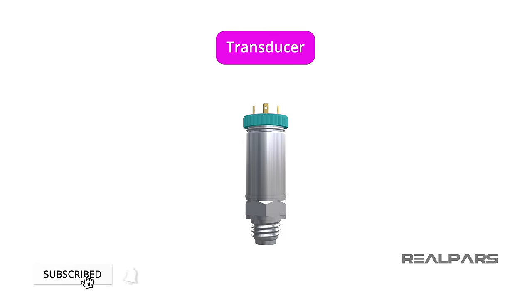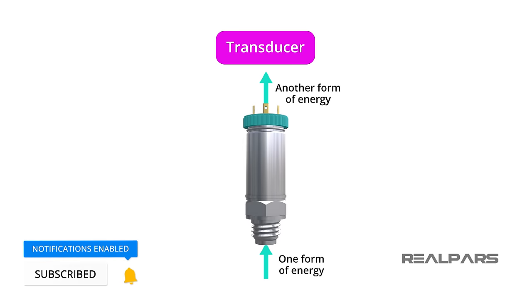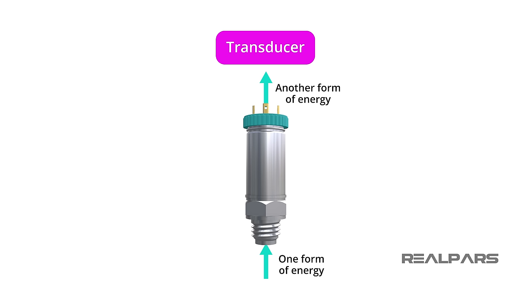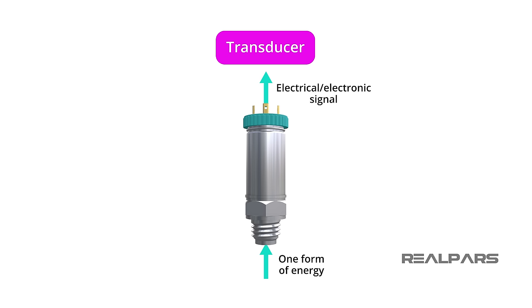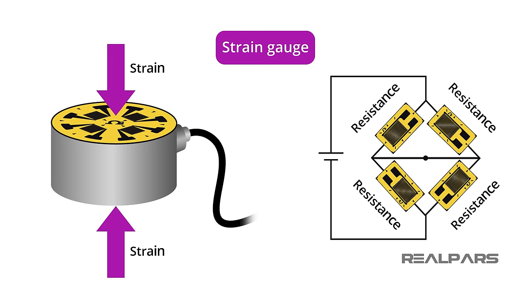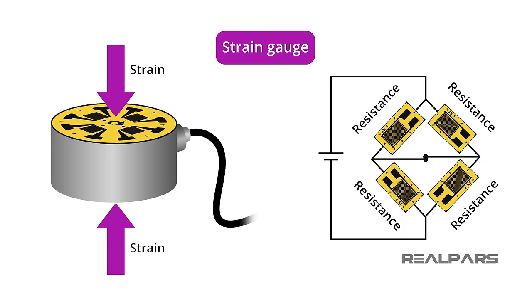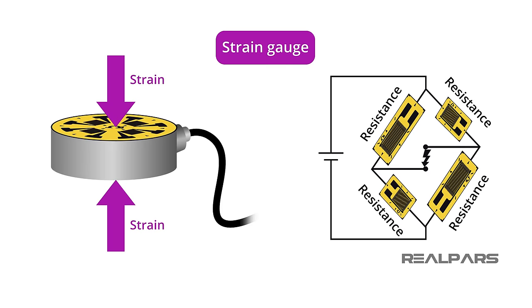A Transducer is a device that converts one form of energy to another. A Transducer provides an output quantity having a specified relation to an input quantity. In the field of instrumentation, the output quantity is an electrical or electronic signal. So, we say that a Transducer measures pressure, load, force, or other states, and converts the reading into an electrical or electronic signal. For example, a Strain Gauge is a Transducer whose resistance value changes proportionally to the strain it experiences.